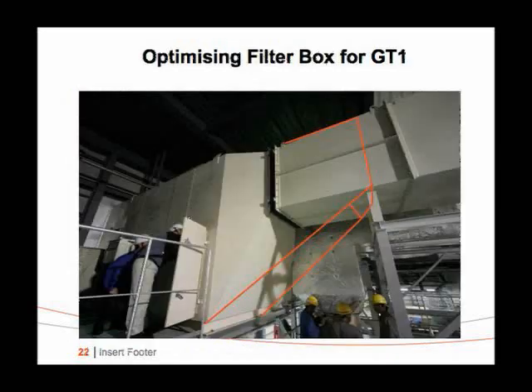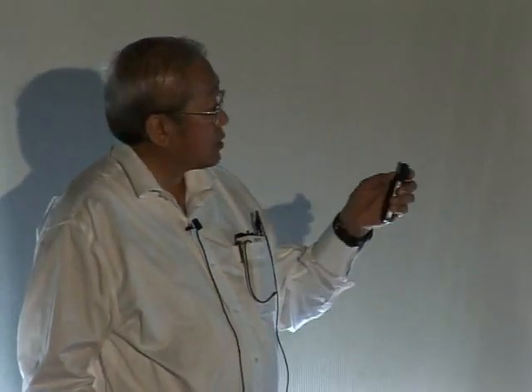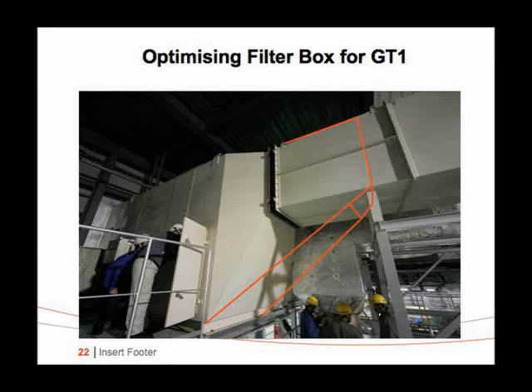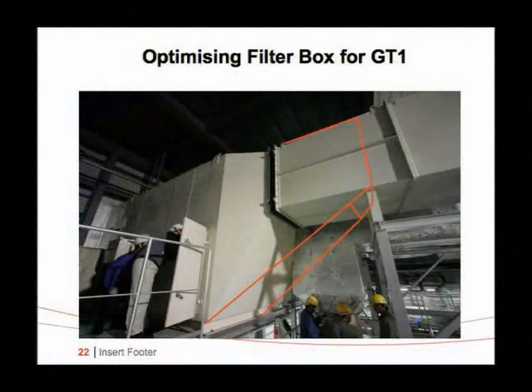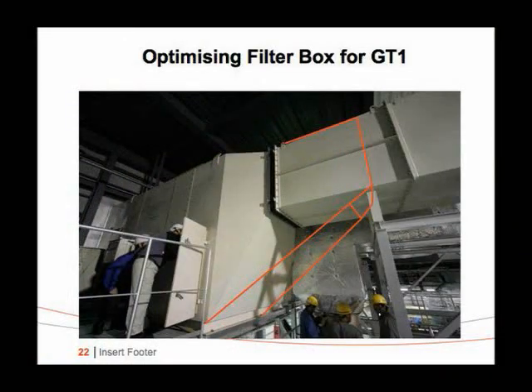Again, air side issues. At any scale, you look at the conventional practice, it's quite bad. This is the inlet to a gas turbine for a fab, which does its own cogeneration. Designed and built by a big Japanese company, I'm told the biggest in Japan. Selection of filters, casing construction, angles inside the airstream that catch the air, etc., etc. Transformations that are extremely sharp, so that's another loss. You need to do something like this, huh? But there's nothing blocking it. I don't think the cost of sheet metal would bankrupt them, but anyway.